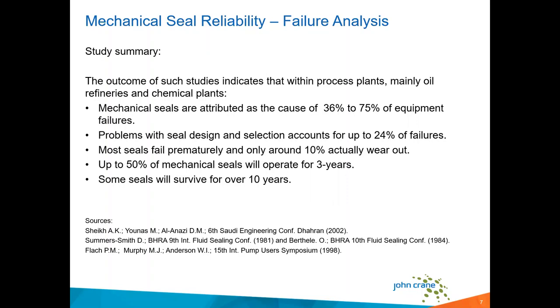But when you look at it now, the problems with the actual seal design really were only up to 24% of those failures. So out of that bigger number, say 75%, roughly 50% was attributed to other factors. Most of the seals in the course of these studies failed prematurely, and only about 10% actually made it to a condition where we can say they wore out, where the faces wore to the point where they could no longer provide a good seal of the process.